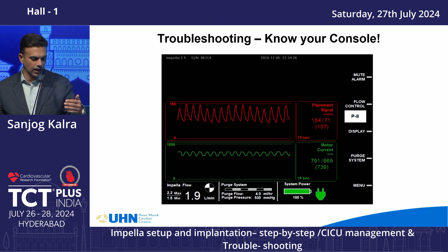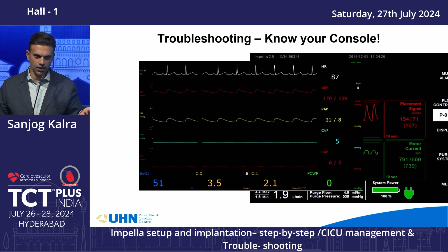So why would the device run into a resistance issue when it's flowing at maximum? Well, if you look at your systolic pressure here, it's actually pretty high and your flow rates are pretty low. So you look at your hemodynamics one more time and confirm that your systolic pressure is sky high. So what's the problem here? The problem is way too much afterload.